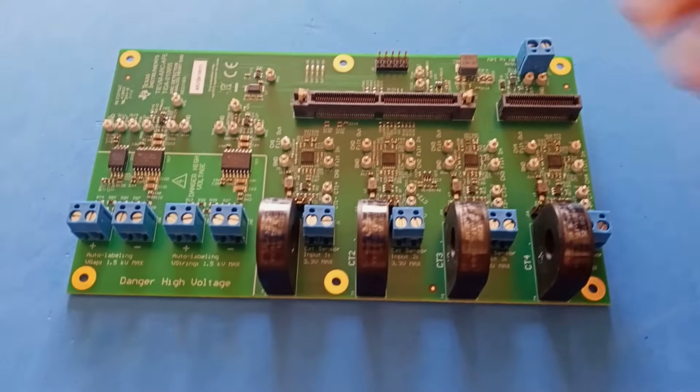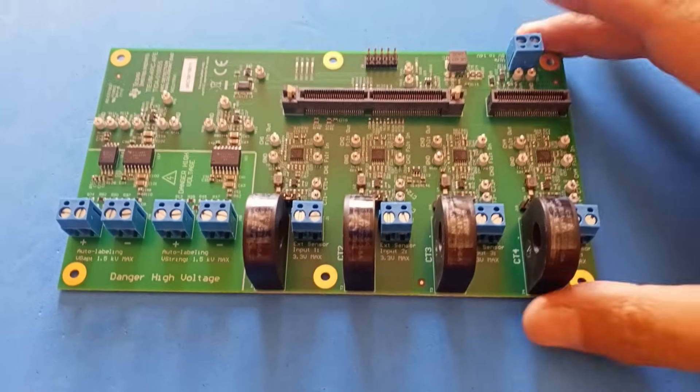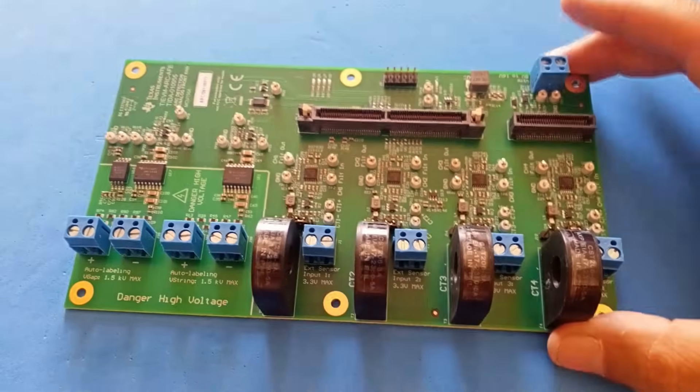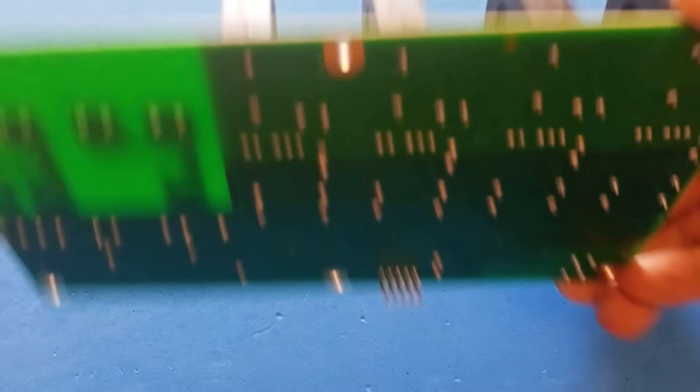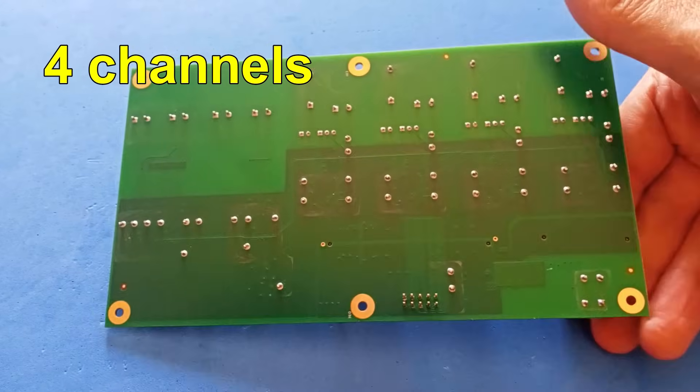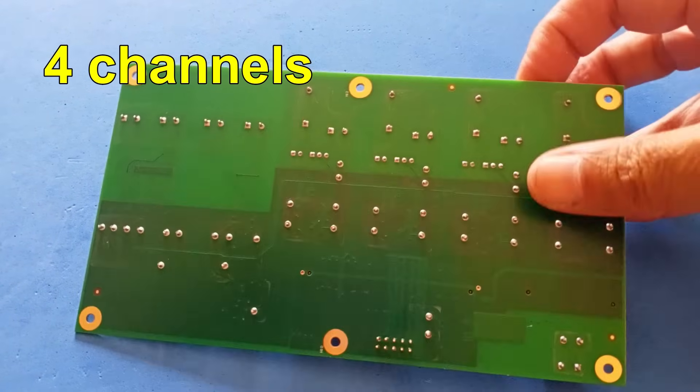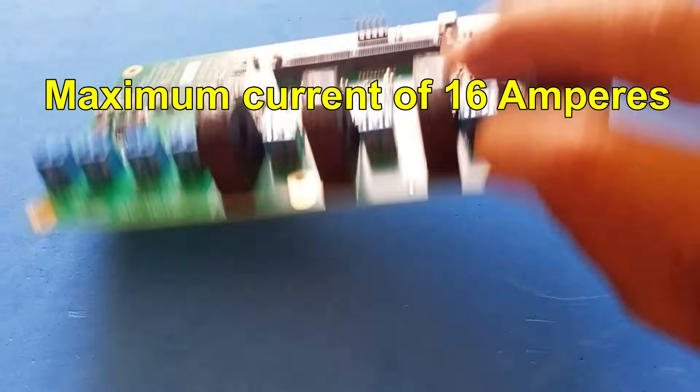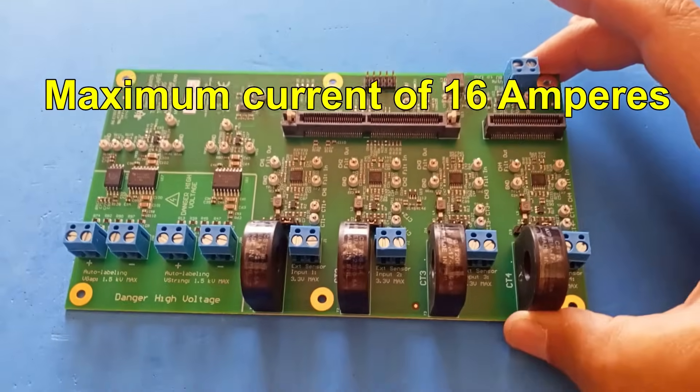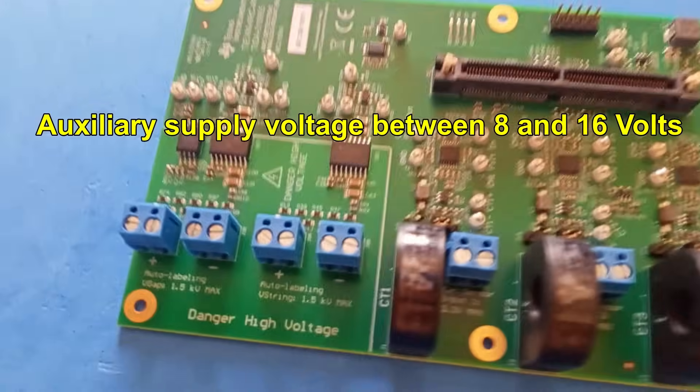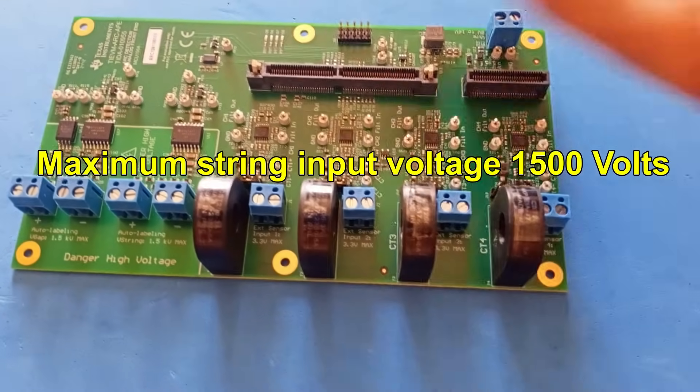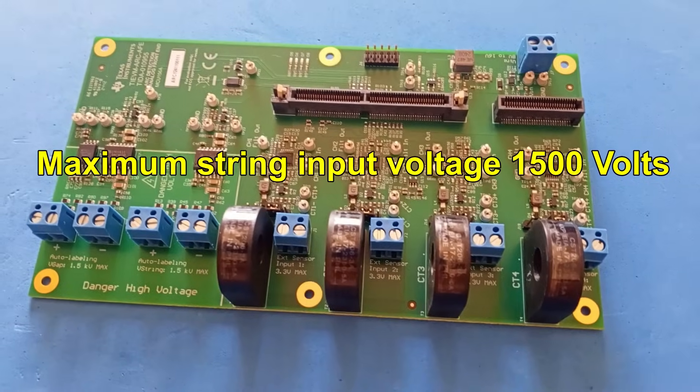Now let's examine the various components of the electronic board. It has four signal acquisition channels, supports a maximum current of 16 amperes. The auxiliary supply voltage ranges between 8 volts and 16 volts, and the maximum string input voltage is 1500 volts.